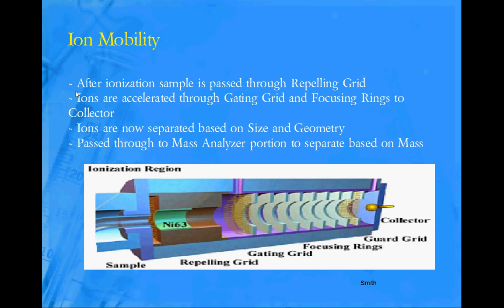Now I want to get into how the ion mobility phase works. What it does is it has the ions that have been evaporated into this drift tube and go through what is a repelling grid, and that gets rid of the weights that don't exactly match up within your known range. It is in a perfectly inert atmosphere, and in that inert atmosphere, the molecules are going to collide with the nitrogen. The bigger conformation, the larger ones that are more unfolded, are going to pass through slower than the smaller ones, the more compact ones, because there are more collisions with those larger conformed molecules. And it lasts for a while and they separate, and then immediately after this are placed into a mass analyzer.